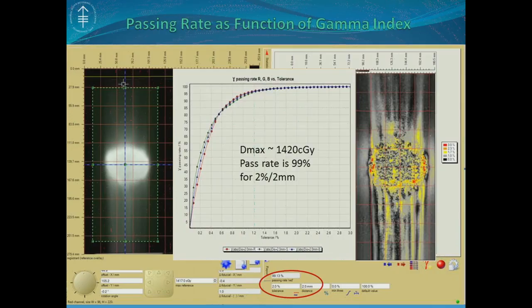Do you remember I showed you earlier, I have many different dose curves for patients. So based on the prescribed patient dose, I can easily choose the appropriate calibration curve to do the analysis. And so here is an analysis of one SBRT lung VMAT, 99% passing rate for 2 millimeter, 2%, and the curve in the middle is the gamma passing rate as a function of gamma index.